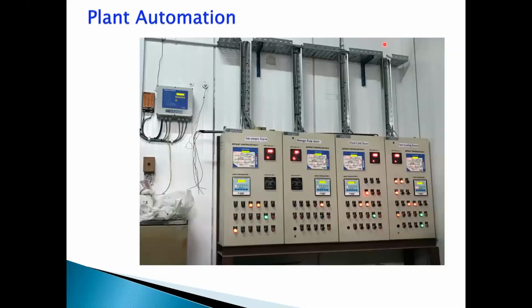Plant automation. The biggest challenge in an ammonia plant is automating your plant room or machine room, that is, automating your condensers, compressors, and pump vessels. There are two ways of doing it. If you're a smaller plant, you can do it using discrete controllers. You can have an independent controller for a compressor and a defrost controller for each independent room, and based on these independent controllers you can switch the compressors on and off automatically. Or you can have relay-based logic or a small control logic to operate the plants.